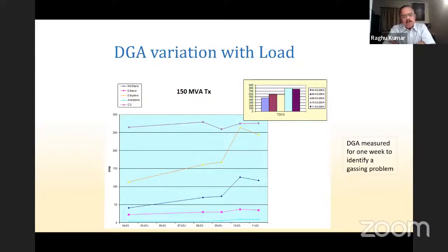So what was done was a continuous monitoring of the gases for a period of 1 week. This particular transformer did not have condition monitoring at that point of time, so physical oil samples were taken and checked every day. And at different loads, the load was adjusted, reduced and increased, and checked. And finally, we arrived at a conclusion.